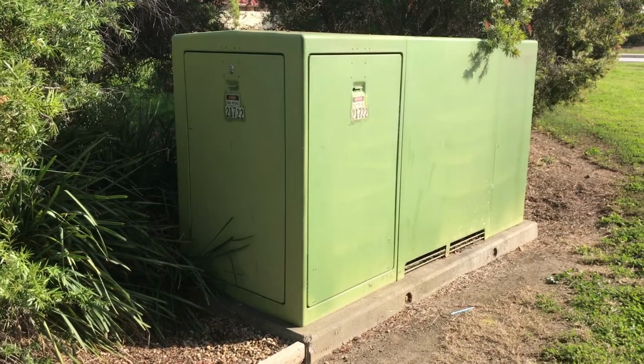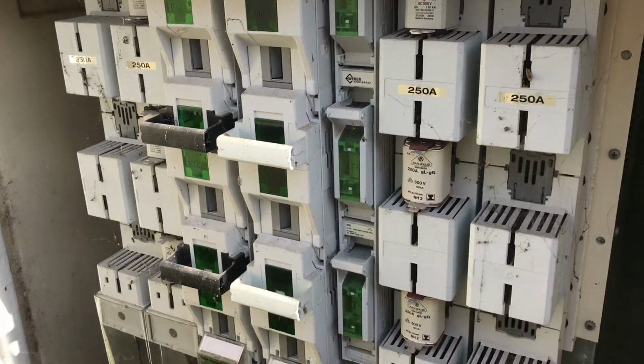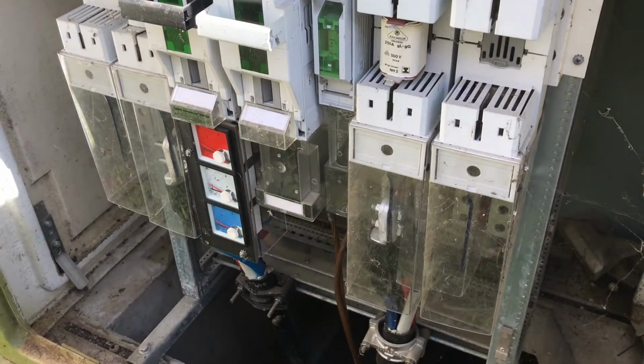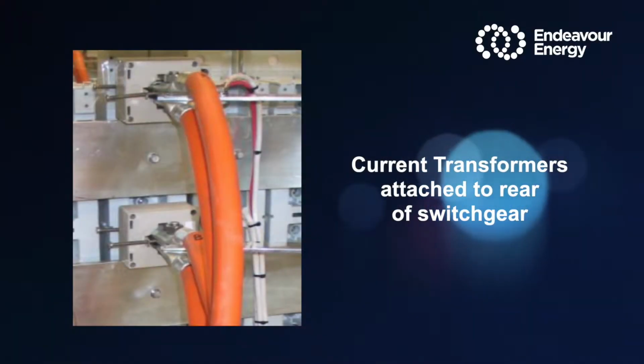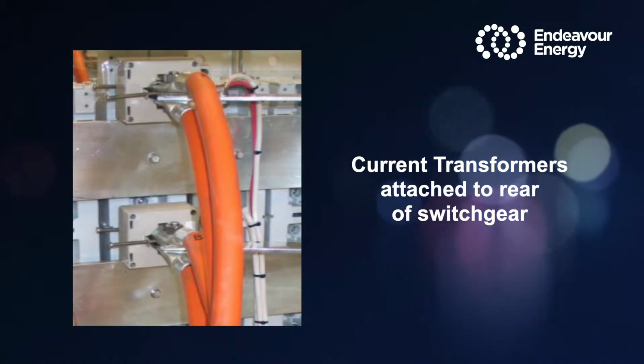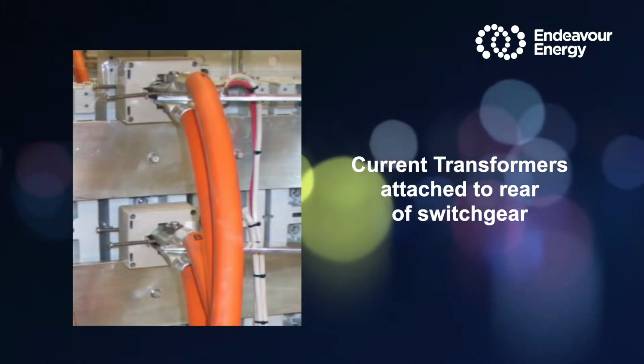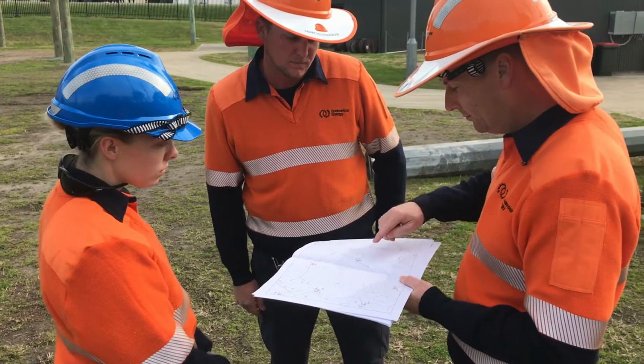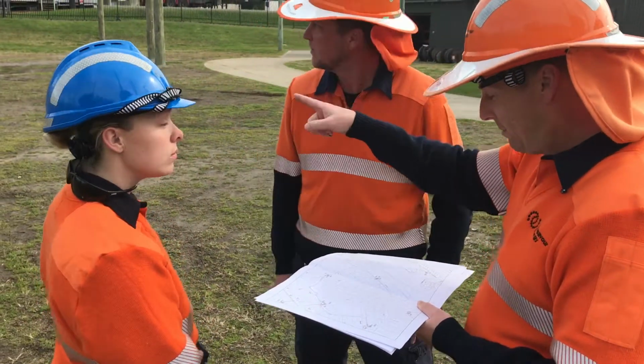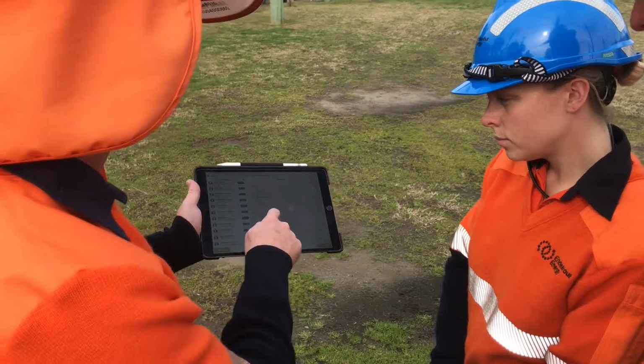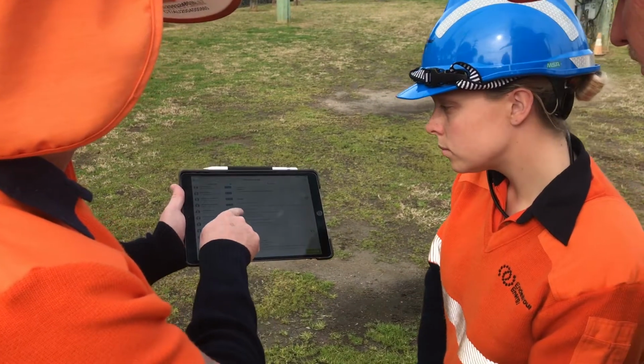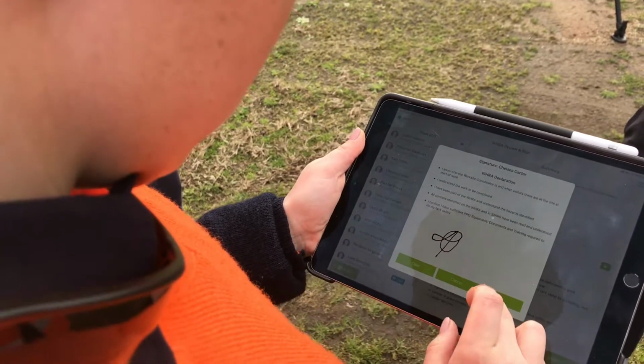Finally, removal or replacement of Weber low voltage switchgear current transformers may only be carried out with the transformer, low voltage fuse strips and distributor connections all isolated. Regardless of these requirements, the final decision to work live or not will be made by the work party on site following completion of the pre-task hazard and risk assessment.